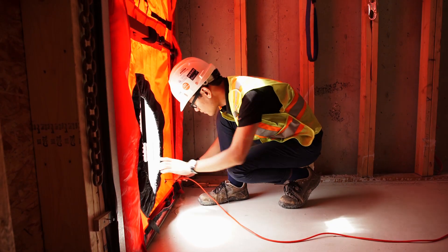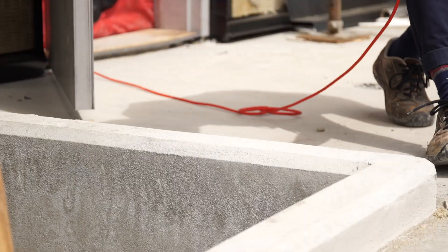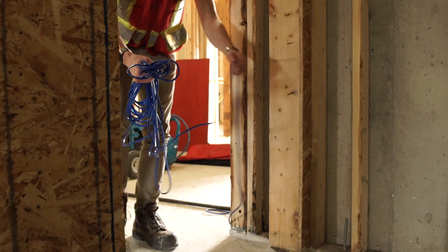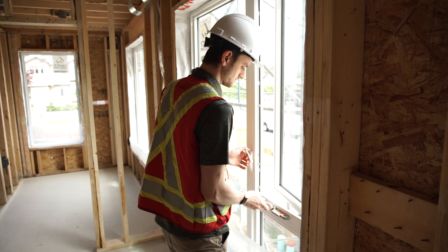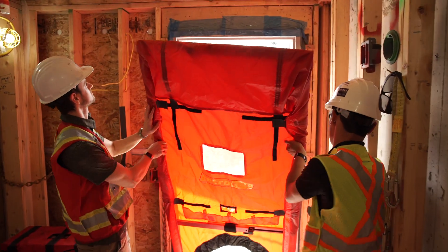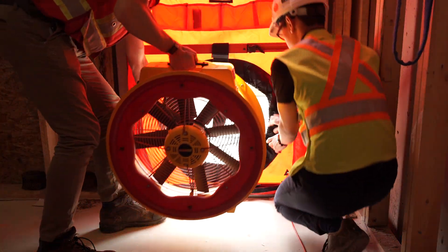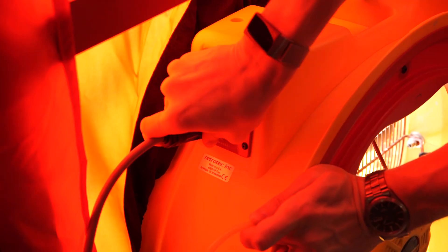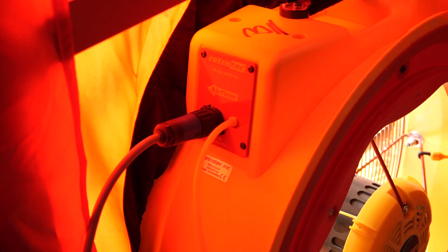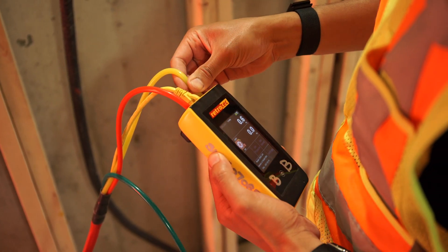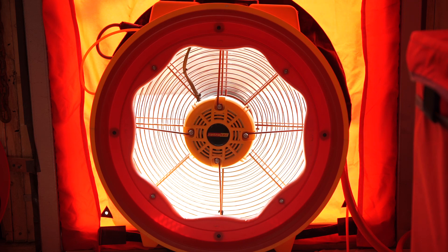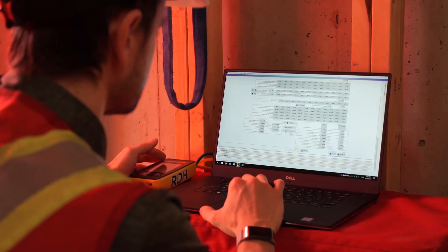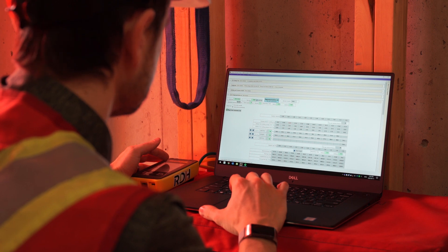For measuring pressure during the test, a small tube known as a pressure tap is run from outside the building back to the pressure sensor known as the manometer. In windy conditions, pressure taps are placed at each building elevation to allow averaging. For the blower fan, a modular door closure is used to seal the door opening around it. Note that the door becomes virtually inaccessible once this is in place, so plan accordingly. The blower fan is installed in the door closure and connected to power, controls, and the airflow sensor. During the test, these calibrated fans are used to pressurize and depressurize the whole building, and their airflow is measured along with the pressure across the enclosure. Software from the test equipment manufacturer can be used to streamline the testing process.